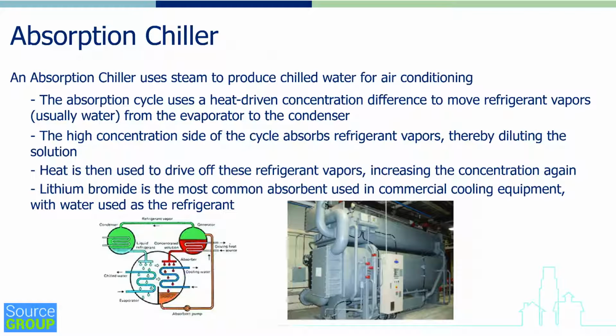Absorption chiller. Absorption chiller is included, again, to show how air conditioning can be made from heat. Seems counterintuitive to make chilled water from hot water, but that's exactly what it does. The absorption cycle uses heat-driven concentration difference to move refrigerant vapors, usually water, from the evaporator to the condenser. The high concentration side of the cycle absorbs refrigerant vapors, thereby diluting the solution. Heat is then used to drive off these refrigerant vapors, increasing the concentration again. Lithium bromide is the most common absorbent used in commercial cooling, with water used as the refrigerant.